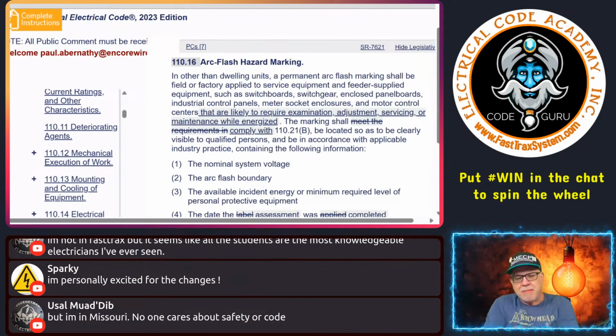Well, I think most all of those things, somebody's going to either do some diagnostic testing or whatnot, so it basically just added this extra language in there for those locations. But it does bring up whether or not all these things have to be done while energized. So that may bring up another argument about, do I require an arc flash hazard marking if I can determine that a piece of equipment does not require examination, adjustment, servicing, or maintenance?